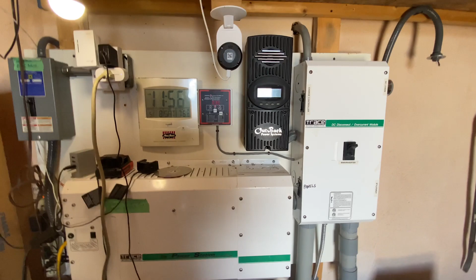So this is an update on the data communication for these 24 volt Gyll lithium-ion batteries. In the previous version of these batteries, there were only 2 ports per battery, basically an RS-485 bus. The latest version has 4 ports: a CAN port, RS-485, and 2 battery dash COM ports.